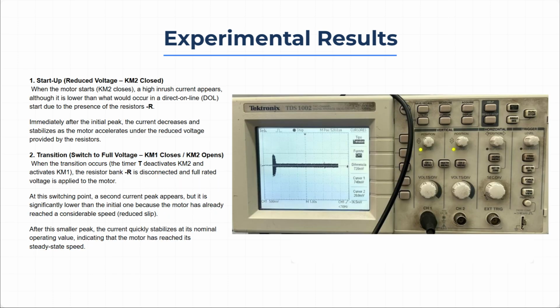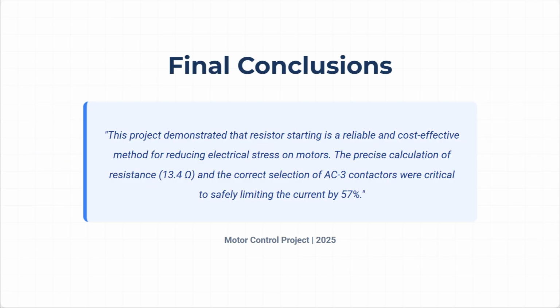Current waveform analysis. On the oscilloscope, we observed two stages. When starting with KM2 closed, a high current peak appeared, but lower than the direct start peak thanks to the resistor bank. During the full voltage transition with KM1 closed and KM2 open, a second peak appeared, significantly smaller because the motor had already reached substantial speed. After this smaller peak, the current quickly stabilized at its nominal value. This project demonstrated that resistor startup is a reliable and cost-effective method to reduce electrical stress on motors. The key to success was the precise calculation of the 13.4 ohms resistance and the proper selection of AC3 contactors, allowing a safe current limitation of 57%.